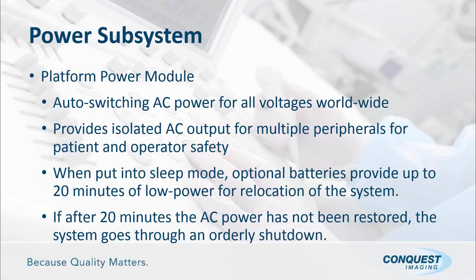And the only disadvantage of that is, well, there are two. The next time you start it up, it'll be a full system startup. And secondly, you have burned all the battery power. So if you're immediately turning it on in a patient's room, and you want to put it in a standby mode, it probably won't go into that sleep mode because the batteries have been used up. You're going to have to give them the appropriate amount of time to recharge.